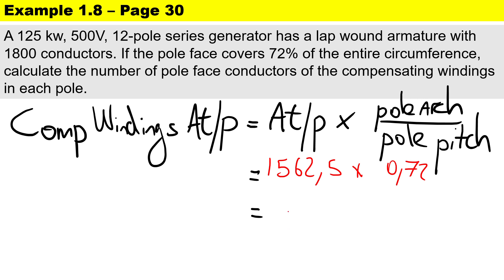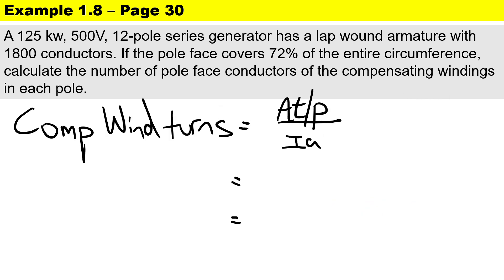Now we want to calculate the compensating winding turns per pole. To do this we need to eliminate the armature current, so we take the compensating winding ampere turns per pole, which is 1125, divided by the armature current of 250. We end up with 4.5 compensating winding turns per pole.